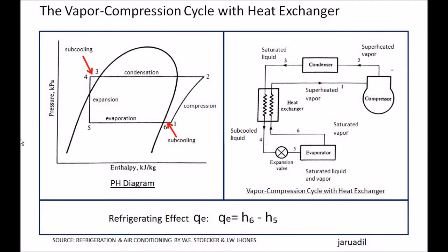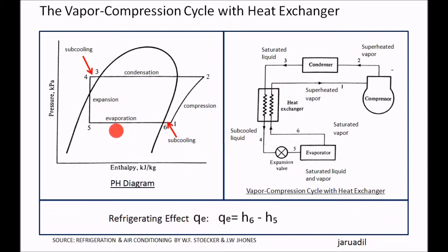Now let us look at the refrigerating effect. What is the refrigerating effect here? The refrigerating effect, by definition, is from 5 to 6 — because that is where the refrigeration cycle actually occurs. The refrigeration happens at 5 to 6. From 6 to 1, there is no refrigeration because that process happens in the heat exchanger. So the refrigerating effect is H6 minus H5.